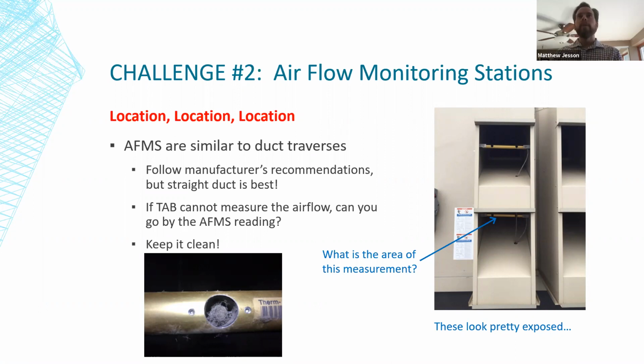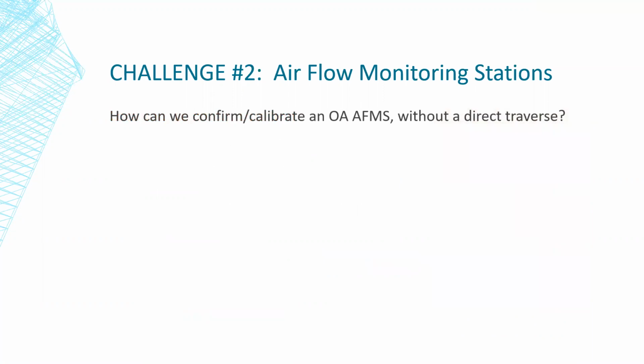All right. So, hey Matt, we do have a question about airflow measuring stations. Excellent. All right, what do we have? Okay. If we have an airflow measuring station to measure minimum outdoor air in a rooftop, such as the Ebtron that we were looking at or something similar, assuming it's engineered to be located in a dedicated minimum outdoor air laminar flow area, why does the TAB apply a correction or adjustment to the airflow measuring station readings, considering the difficulties of measuring outdoor airflow for an RTU?